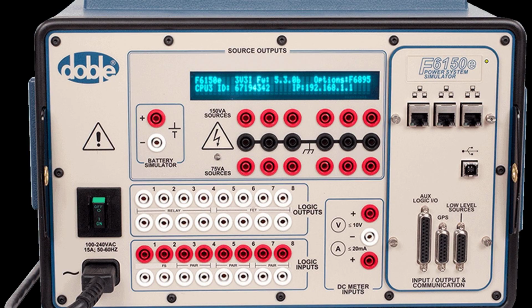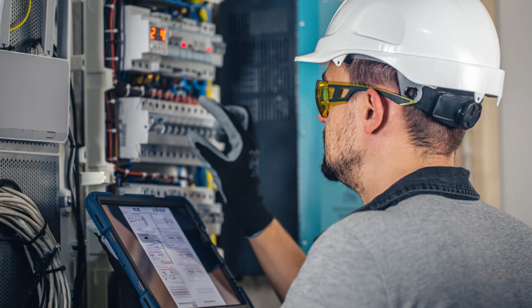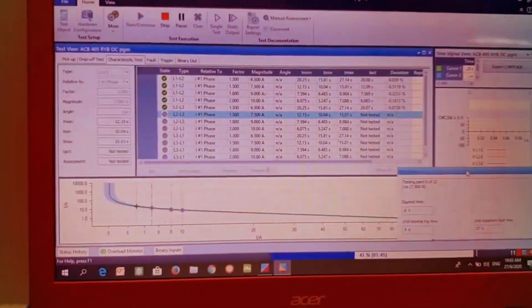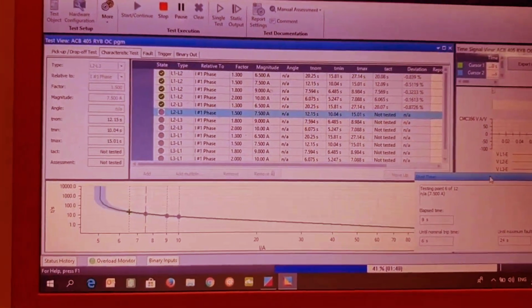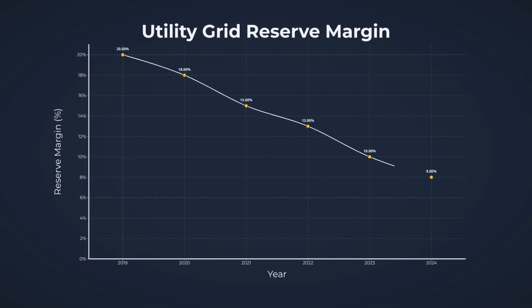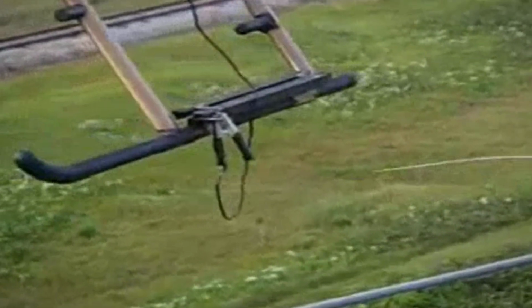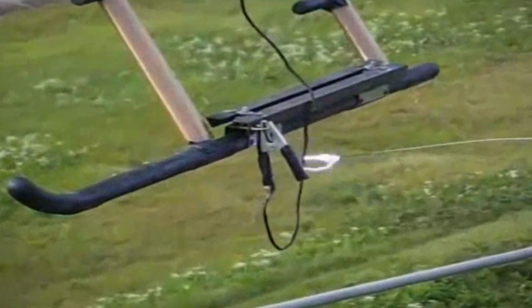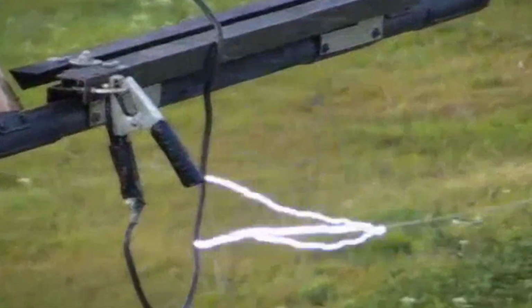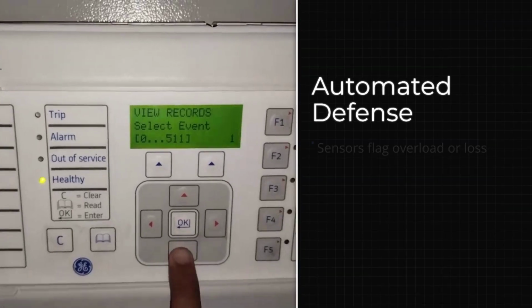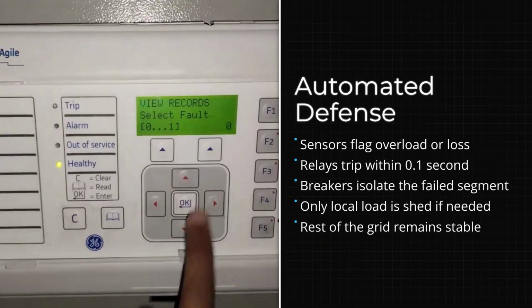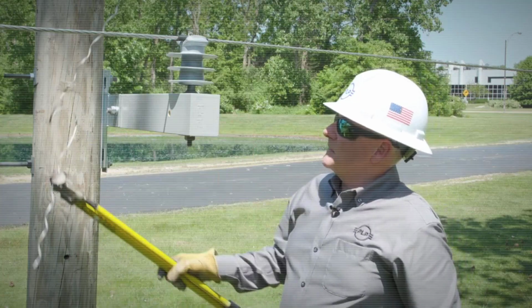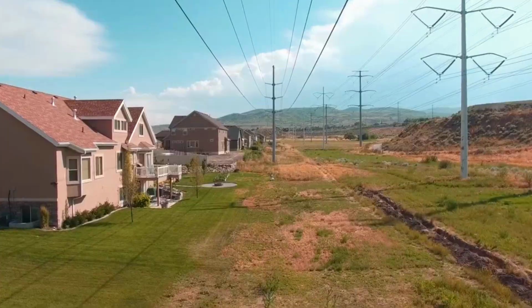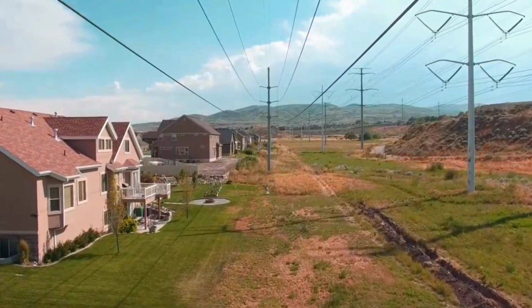Protective relays are calibrated to trip at precise thresholds, typically 105 to 120% of rated current, ensuring that only a true fault or a severe imbalance can trigger disconnection. If reserve margins fall below 10%, automated load-shedding protocols cut power to non-critical circuits within seconds, stabilizing frequency and preventing under-voltage collapse. These responses are executed without operator discretion. Relay logic and preset thresholds dictate the outcome. The system is engineered to contain failures by sacrificing limited load, preserving the integrity of the wider network.